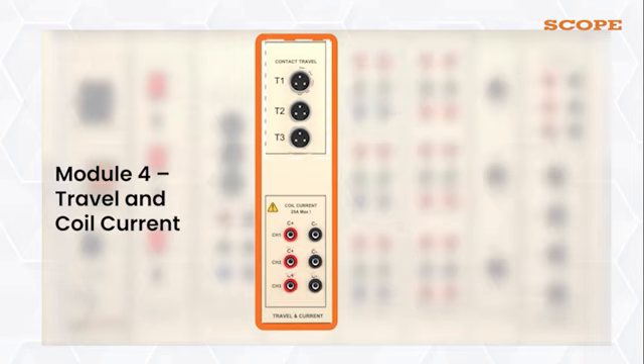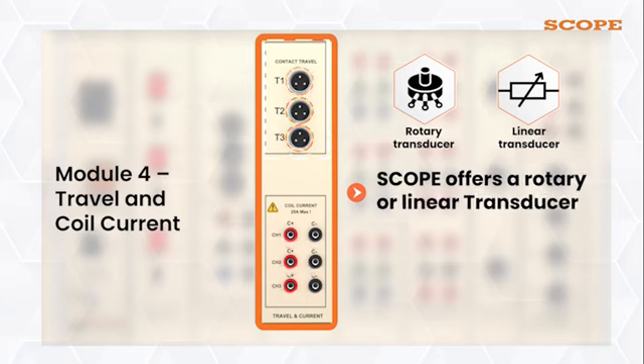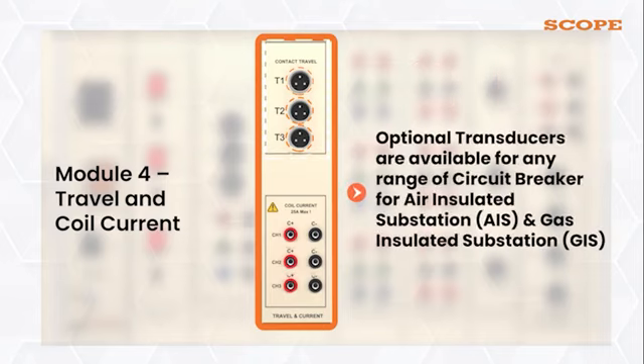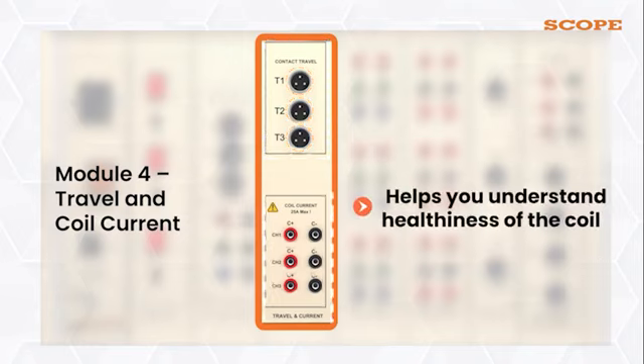You can measure the travel of all 3 poles simultaneously. Scope offers a rotary or linear transducer as per the circuit breaker mechanism. Optional transducers are available for any range of circuit breakers for AIS and GIS. Coil current measurement is also an important parameter. It helps you to understand the healthiness of the coil.